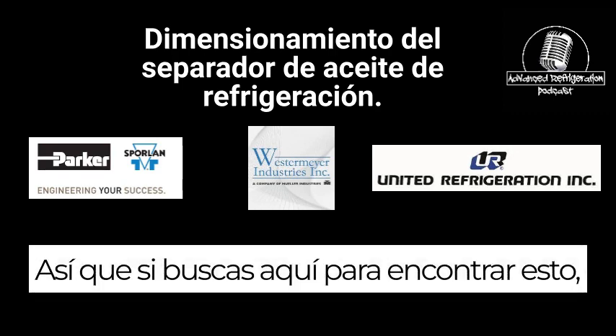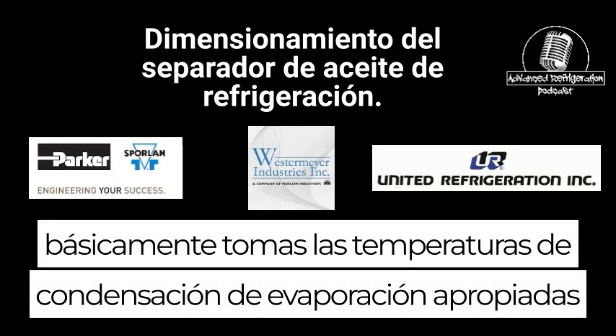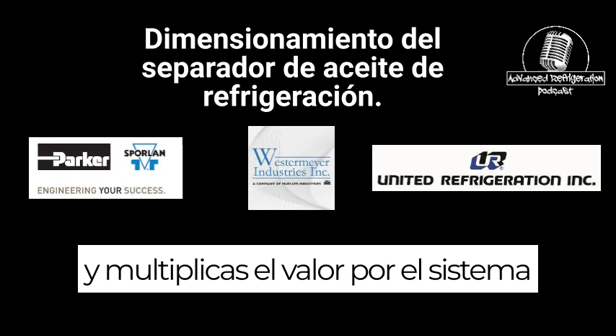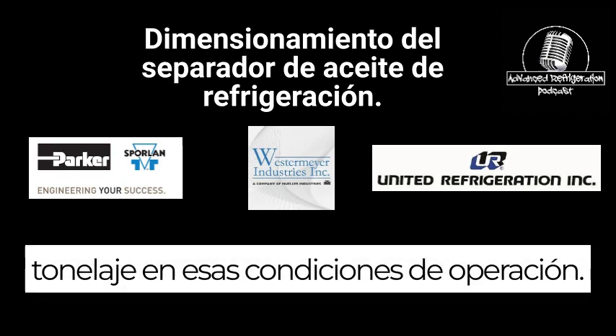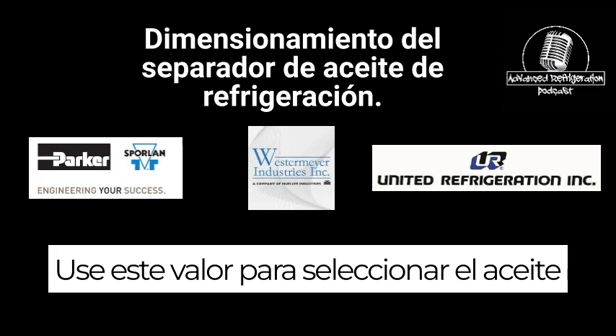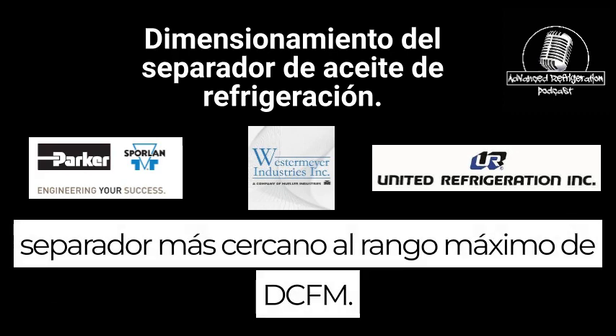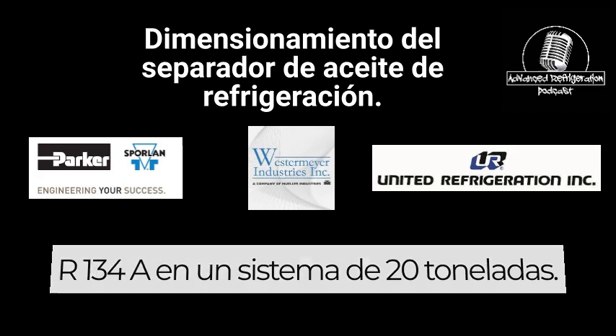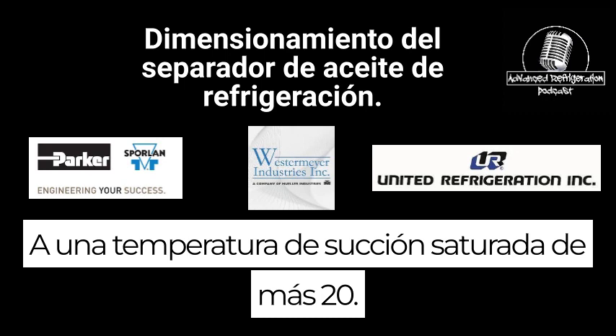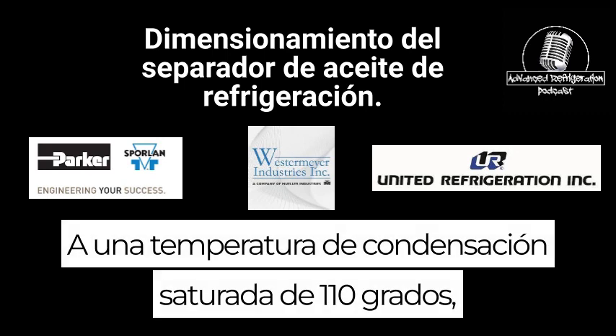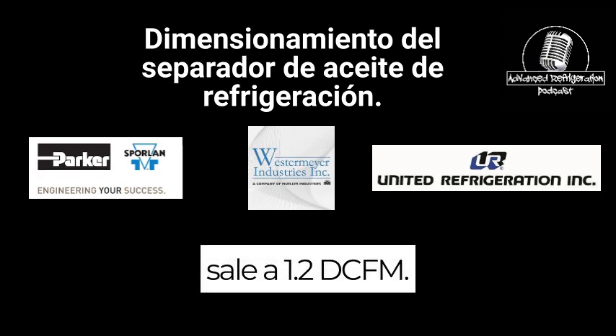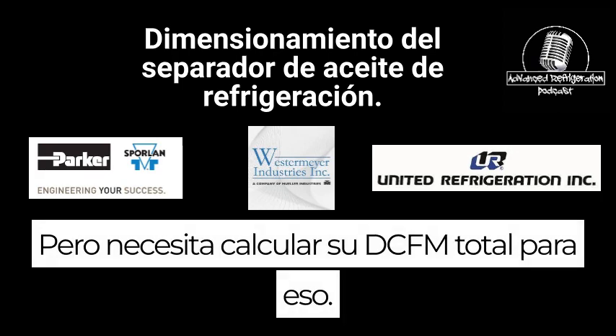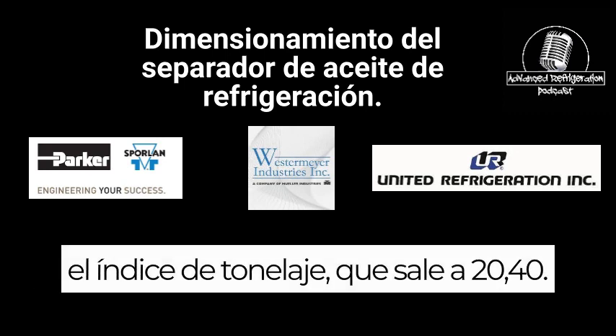So if you look here to find this, you basically take the appropriate evaporating and condensing temperatures and you multiply the value by the system tonnage at those operating conditions. Use this value to select the oil separator nearest to the maximum DCFM range. And so we go through here and you've got R134A at a 20-ton system at a plus 20 saturated suction temperature at 110 degree saturated condensing temperature. It comes out to 1.02 DCFM, but you need to calculate your total DCFM for that. So then you need to take that times the tonnage rating, which comes out to 20.40.